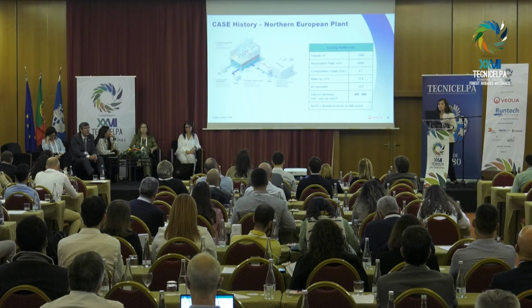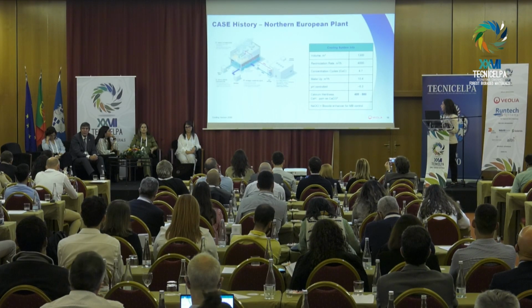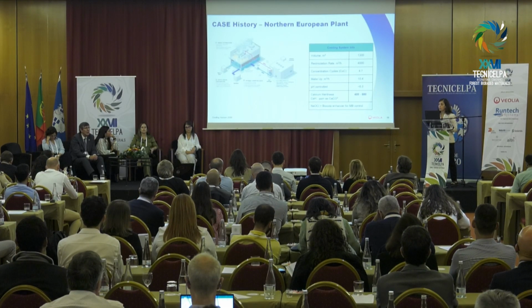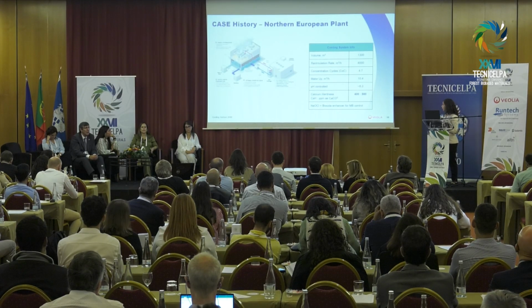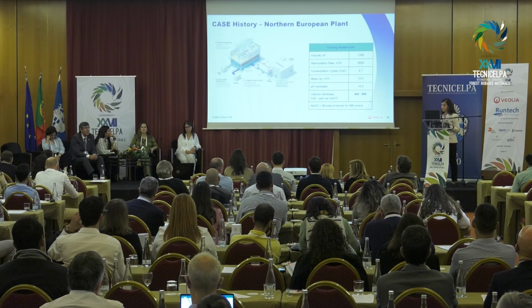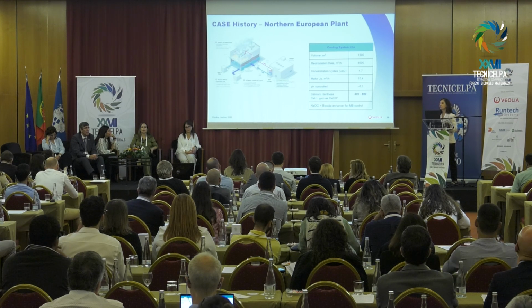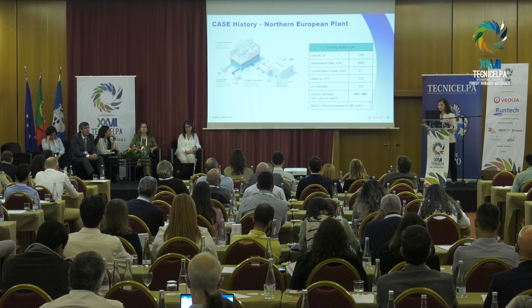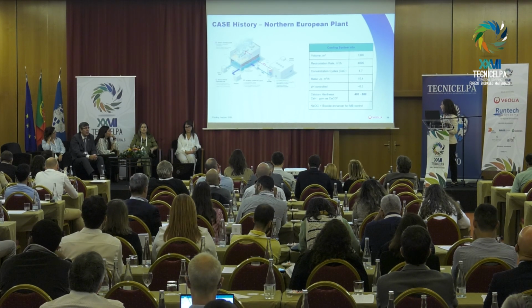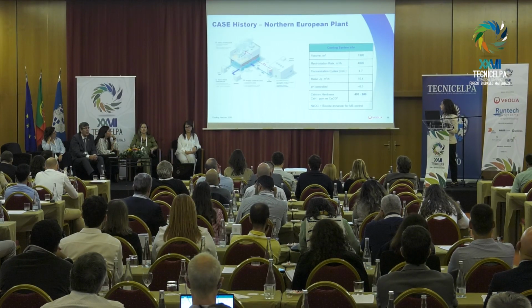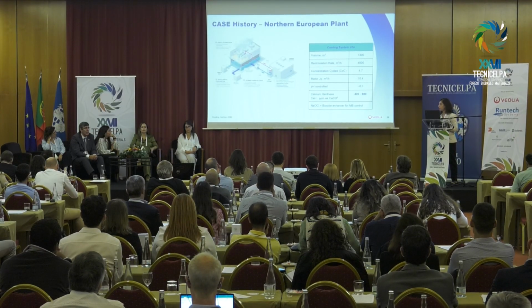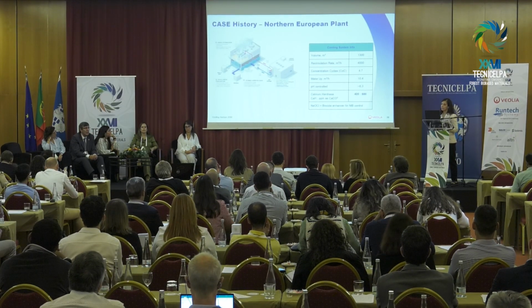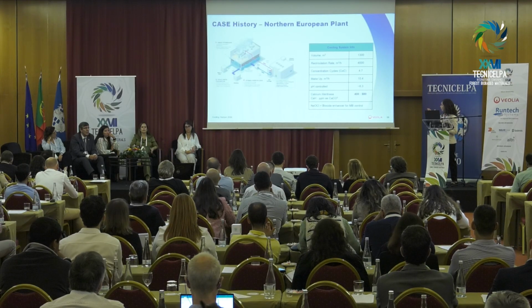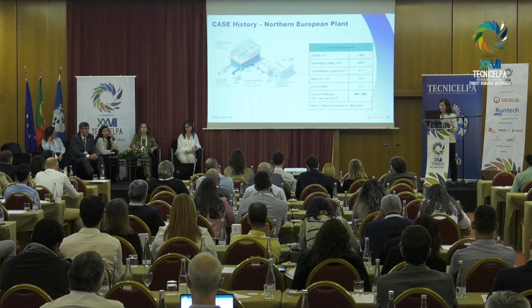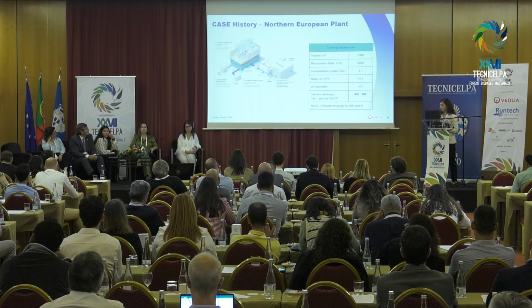We know that in pulp and paper mills, especially process cooling towers, we could have much lower concentration cycles, meaning we are using much more fresh water. The limiting factor of this circuit was calcium hardness, at 400 to 500 ppm.